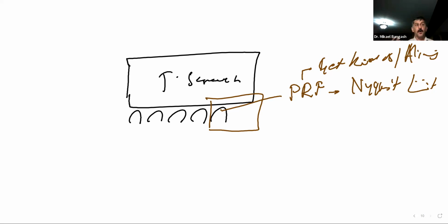The system still recorded it, but misrepresented it as if you had a positive Doppler shift, or as a negative Doppler shift. Or if we had a negative Doppler shift, it misrepresented it as a positive Doppler shift. But this knob also has another function, and that other function is your wall filter.